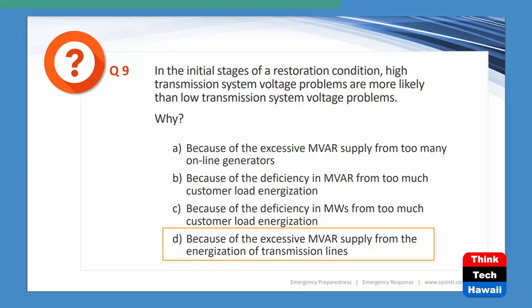And you may find some open breakers on the other side of that. You may see an energized system, which is outside your area, or maybe in your area where you have a partial blackout. But in order to restore your system, you're going to start with some basic generation, black start units, small generators, or maybe you're going to energize from outside your system, and start working your way down your transmission system. So transmission circuits, whenever they are lightly loaded or have no load at all, act as giant capacitors. And once you're energized and you put voltage on them, those lines begin to generate VARs, which will, again, raise your voltage.